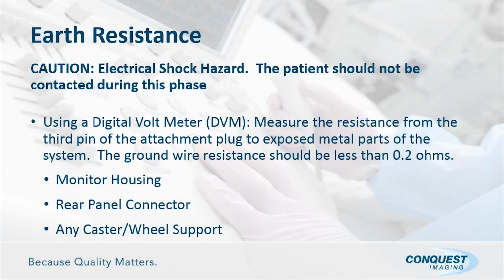Then we check earth resistance, and earth resistance is a really important one. This is basically measuring the resistance from the system to the wall, and you can do it one of two ways. You can use a digital voltmeter, and just by disconnecting or using ground on the system, you can take the third pin of the attachment plug and a metal part of the chassis and measure the ground resistance.